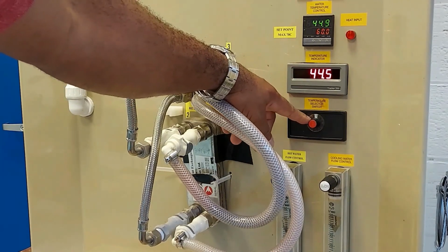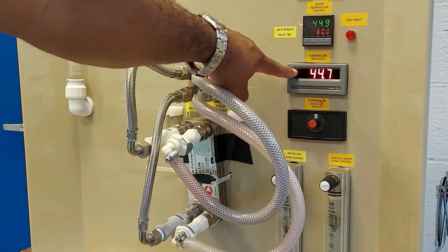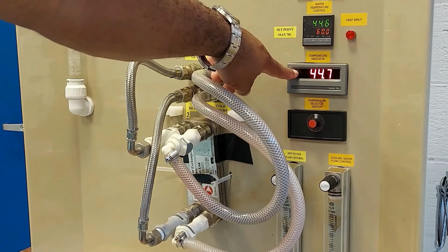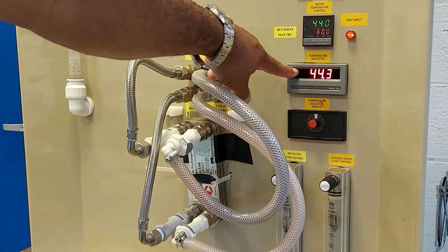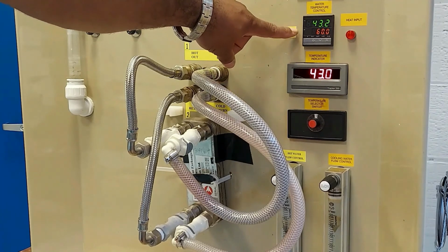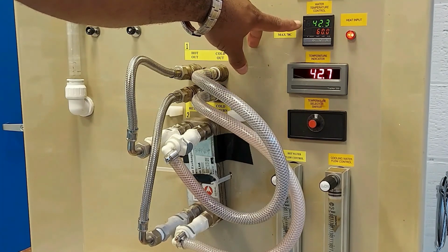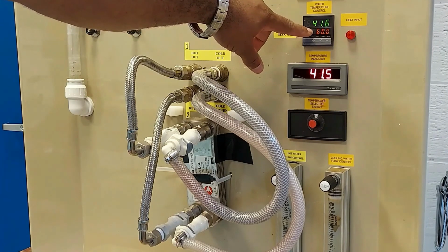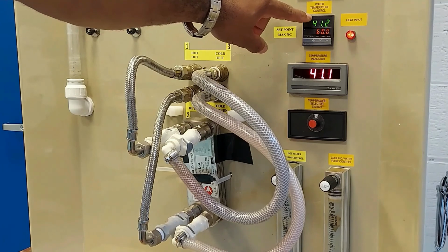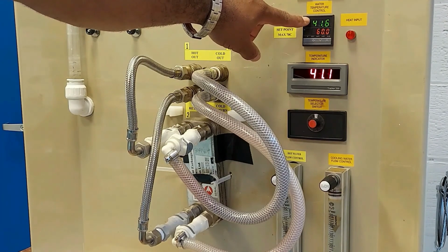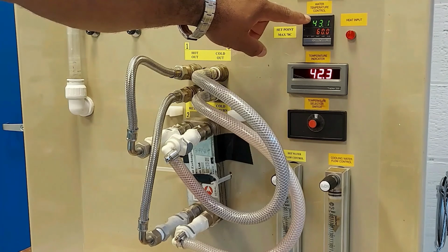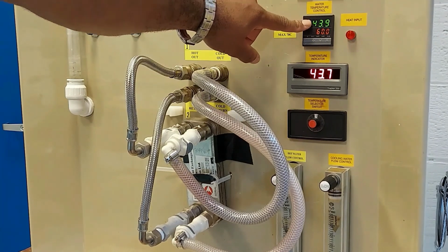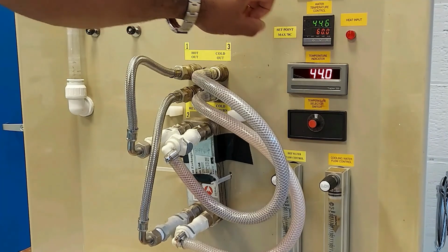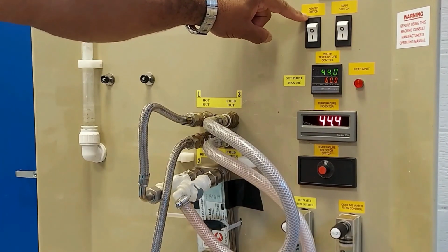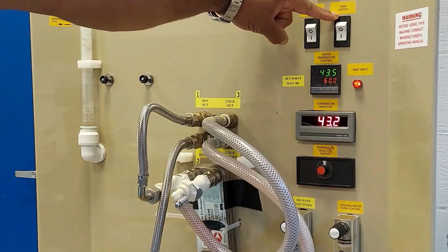Above the thermocouple switch, we have our digital display that shows us the actual temperature at the specific thermocouple, whether it's 1, 2, 3, or 4. Above, we have our display dial that shows us our preset temperature, that is 60 degrees, and the temperature in the green shows us the actual heater temperature. So we would wait until this section gets to 60 degrees for us to observe stabilization. Next we have our heater switch and main switch, which turns the machine on and off.